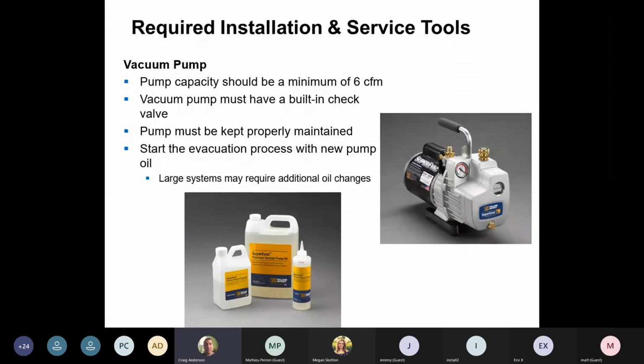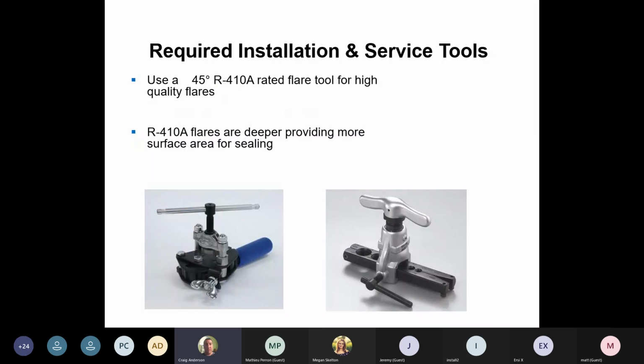Required installation service tools. So mini splits, you'll notice all mini splits have flare nuts on them. So make sure that your flaring tool is a 45-degree 410A rated flare tool. There are different flaring tools that will not give you a 45-degree. So if you bought one at Canadian Tire or Princess Auto, take a look at it. Make sure that it's rated for 410A, and it'll do a 45-degree flare. 45-degree flares are a little deeper to get that sealed on the flare nut.